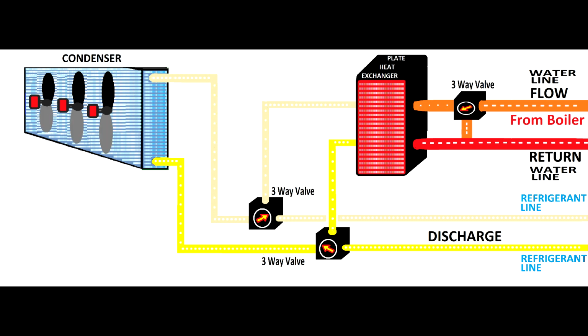In that case, the temperature ratio won't be very good, and the boiler will have to compensate to send a kind of warmish water into this plate heat exchanger, and the plate heat exchanger will boost the temperature. So the plate heat exchanger will have a very small ratio for the water temperature, like you can play with only 2 or 3 or 4 or 5 degrees ratio.